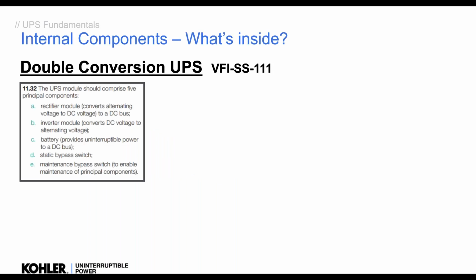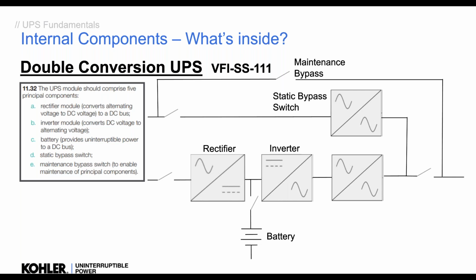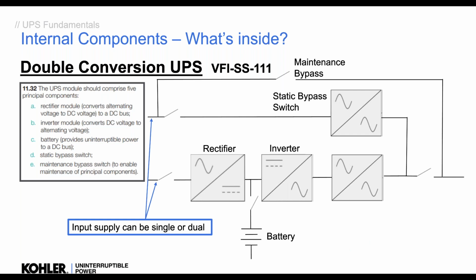So with the UPS fundamentals, HTM talks about 2 types of UPS, a double conversion UPS and a single conversion UPS. Now the double conversion UPS should be classified as VFI SS 111 under the standards. And it should have a rectifier, an inverter, a battery, a bypass, and a maintenance bypass switch. And that's laid out like this. So typically the mains comes in here, and it is typically 1 or 2 supplies. And if it's 1 supply, we just link it out. Power comes in through the rectifier, through the inverter, through the static switch, and out to the load. We have a static bypass available if there's a problem or we need to bypass it. And ideally a maintenance bypass, so we can bypass as necessary with that.